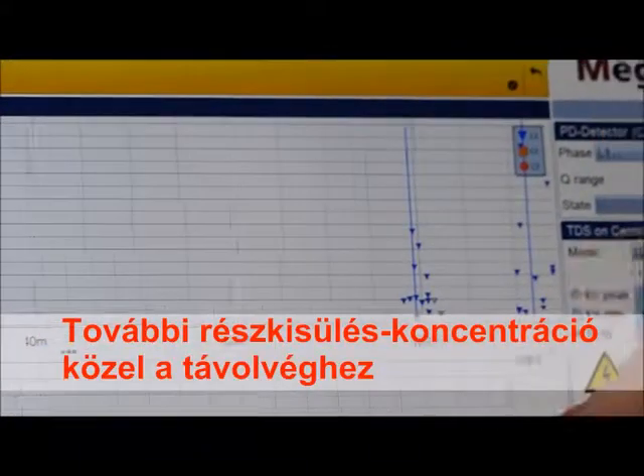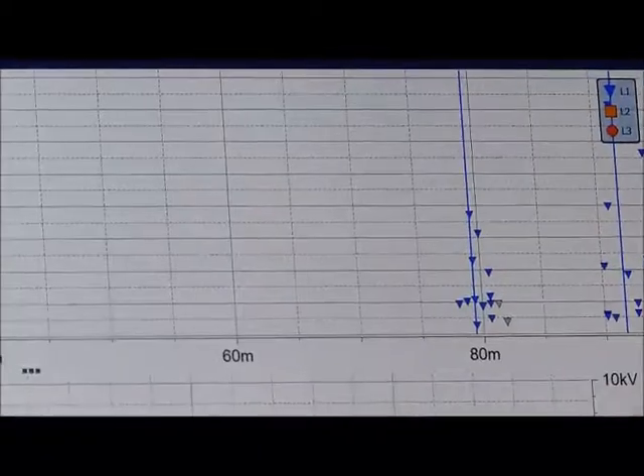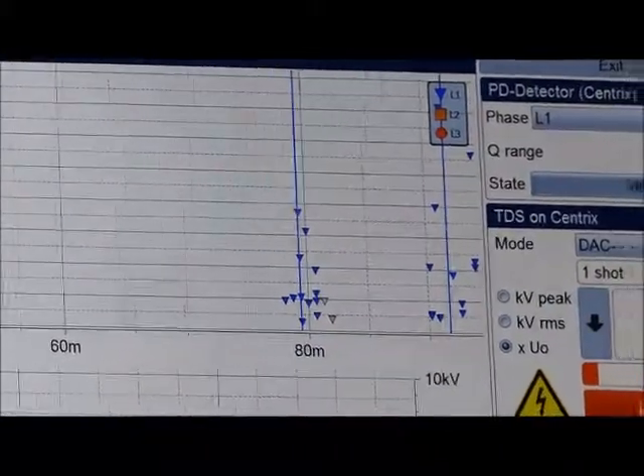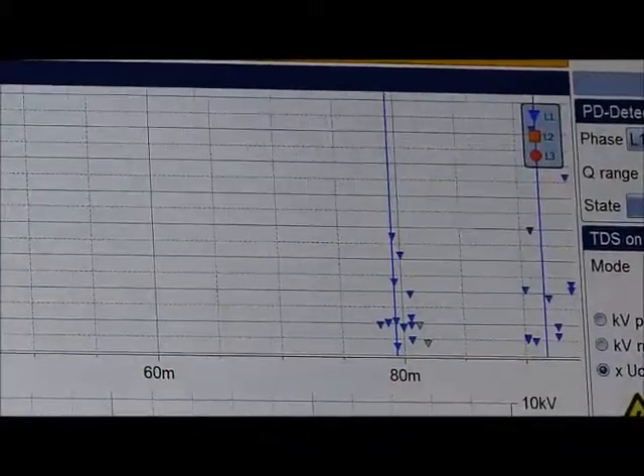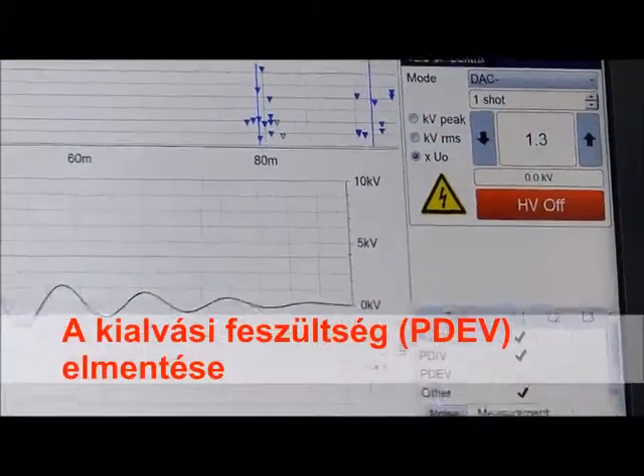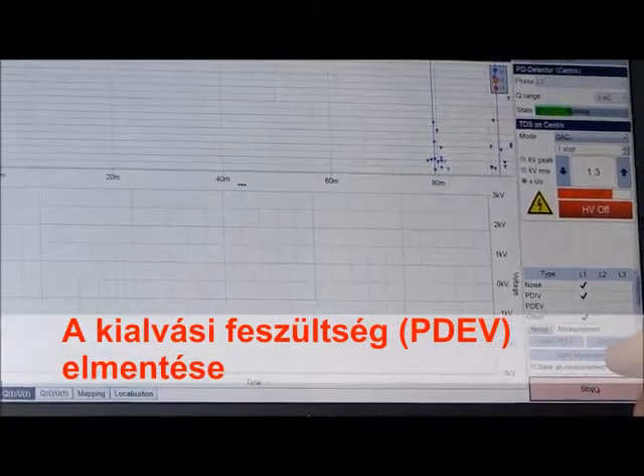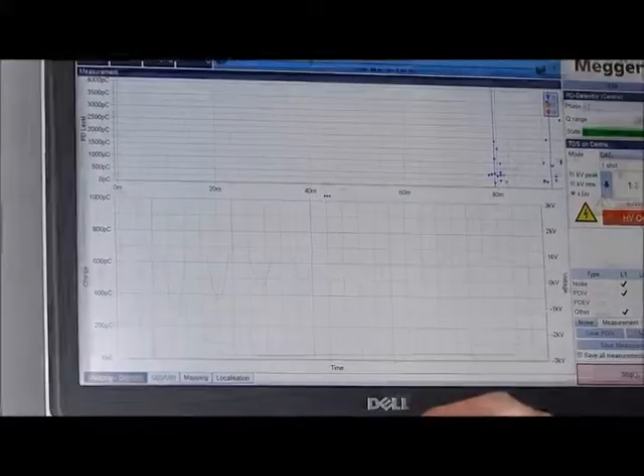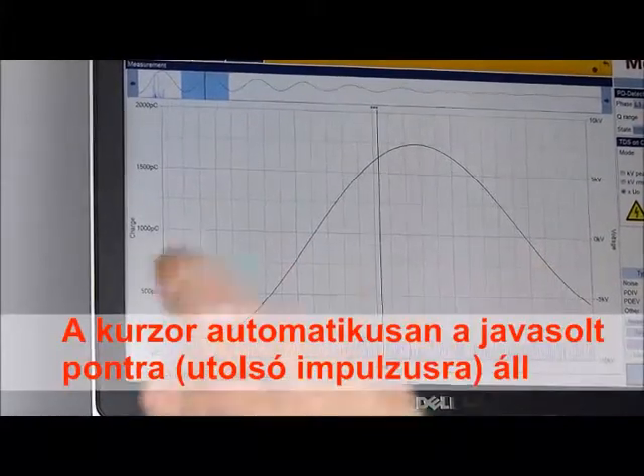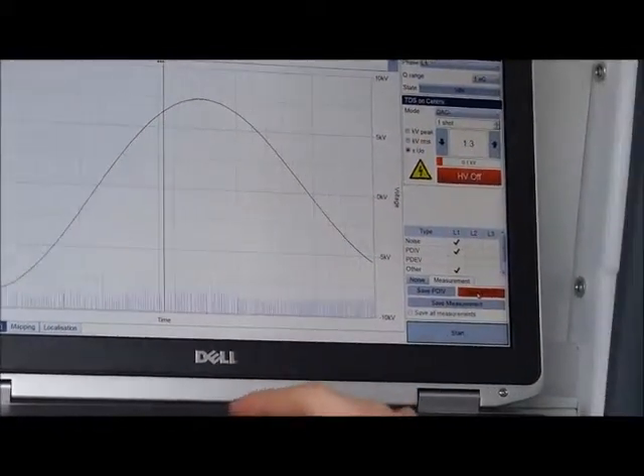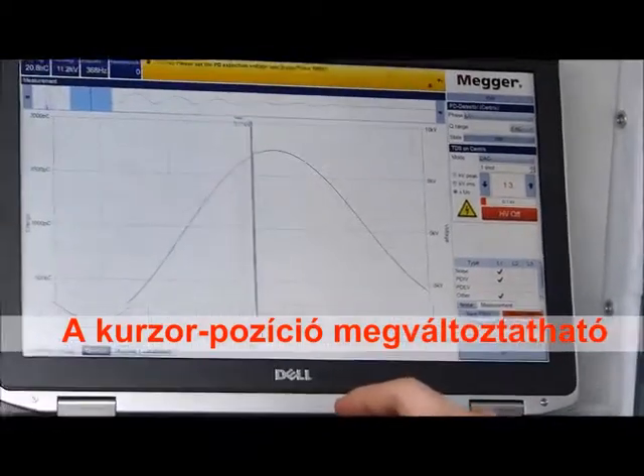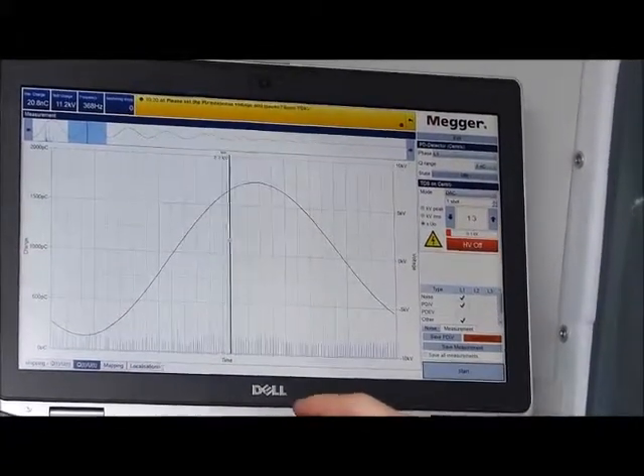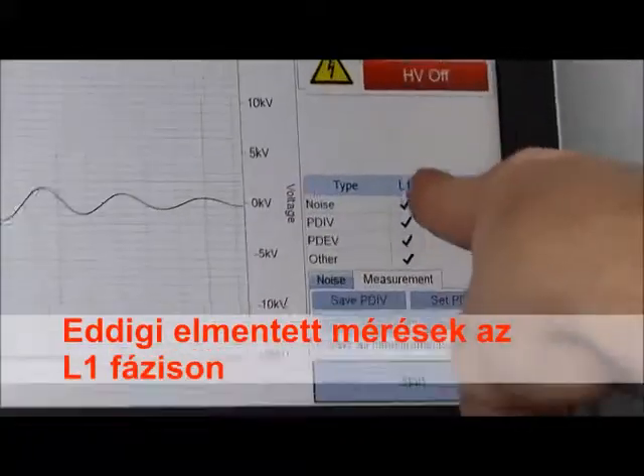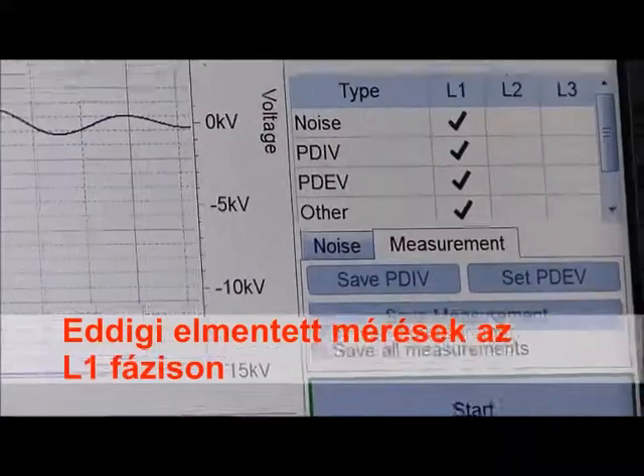So it seems we have another concentration more or less at the end, but if the determination is the same like here, maybe it's discharging to the cabinet. Also like with the OWTS, we have to save the partial discharge extinction voltage for an accurate evaluation, an additional cursor, but here the software automatically jumps to the most recommended last pulse. And if I now would remove that cursor, you see, okay, and the noise measurement, we have saved the inception, we have saved the extinction voltage, so all done.